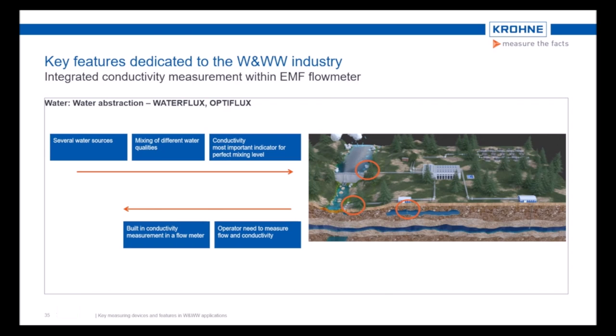Many operators extract the raw water from different sources. Surface water from dams or riverbank filtrate are as much a part of it as groundwater from different aquifers. An indication of the mostly different qualities of the raw waters can often be given through the conductivity. The EMF flow meters, which are already installed in the pumping stations of the water abstraction wells, offer an integrated conductivity measurement as a standard. This enables an evaluation of the quality values and gives an indication of the quality of the raw water.